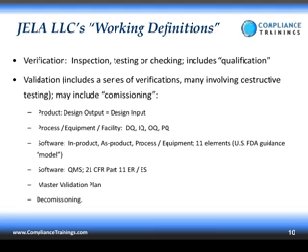If we look at the 820.30 for devices, under F, it says design verification. Each manufacturer shall establish and maintain procedures for verifying the device design. Design verification shall confirm that the design output meets the design input requirements. The results of design verification, et cetera, are included in the DHF. Okay, so how do you confirm? How do you document results? How do you verify? Well, my point is you do these things by testing, by inspecting, by developing a checklist and checking off the items on that checklist against requirements. That's my definition of verification, basically testing and inspection.